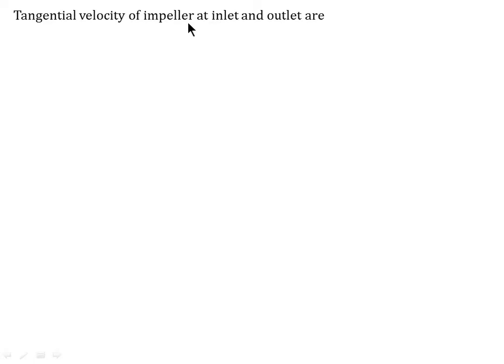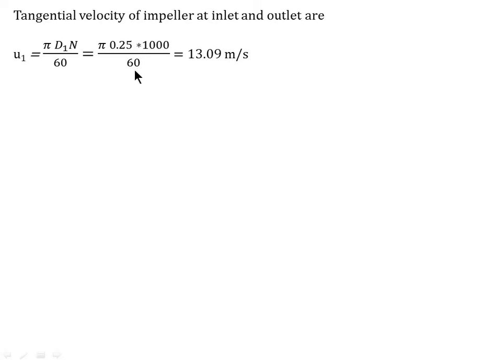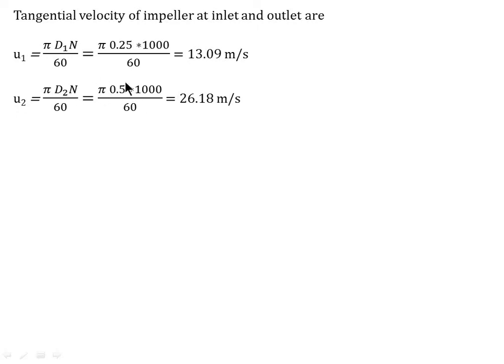Tangential velocities at inlet and outlet are calculated using the formulas: U1 equals pi·D1·N divided by 60, and U2 equals pi·D2·N divided by 60. So U1 equals pi × 0.25 × 1000 divided by 60, giving U1 equals 13.09 meter per second. Similarly, U2 equals 26.18 meter per second, using D2 equals 0.5 meter.